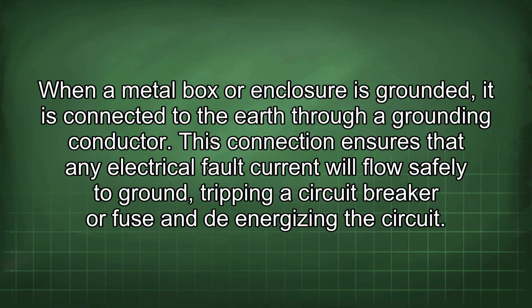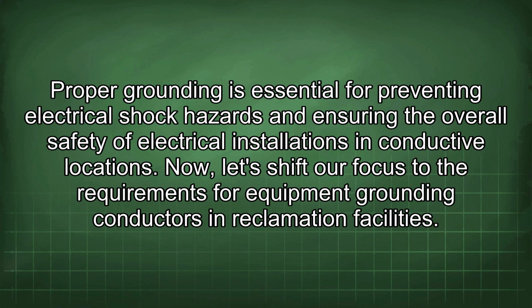When a metal box or enclosure is grounded, it is connected to the earth through a grounding conductor. This connection ensures that any electrical fault current will flow safely to ground, tripping a circuit breaker or fuse and de-energizing the circuit. Proper grounding is essential for preventing electrical shock hazards and ensuring the overall safety of electrical installations in conductive locations. Now, let's shift our focus to the requirements for equipment grounding conductors in reclamation facilities.